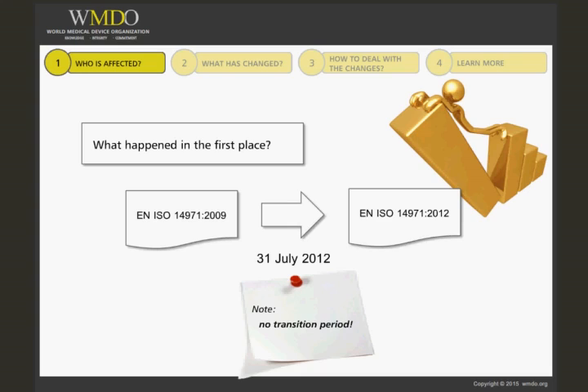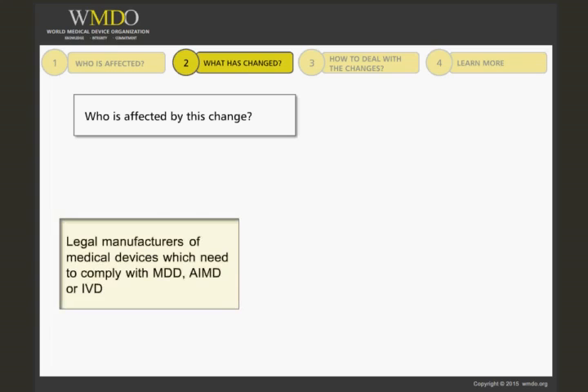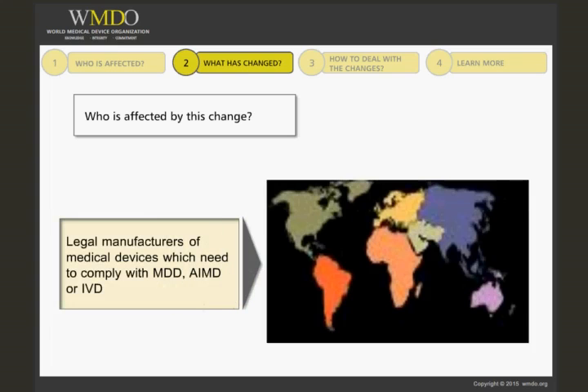As such, it is not a change to the basic content of the standard. EN ISO 14971:2012, as of July 31st 2012, applies as a harmonized standard for all legal manufacturers placing medical devices on the market in Europe. Basically, compliance with this standard provides the so-called presumption of conformity with EU regulations regarding medical devices as regulated by the European medical device directives: MDD, AIMD, and IVDD.